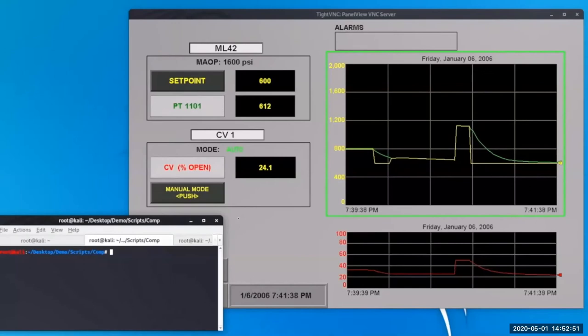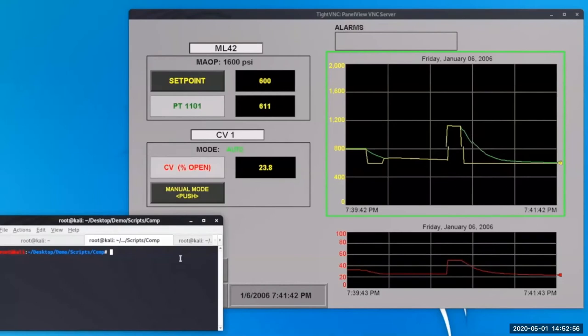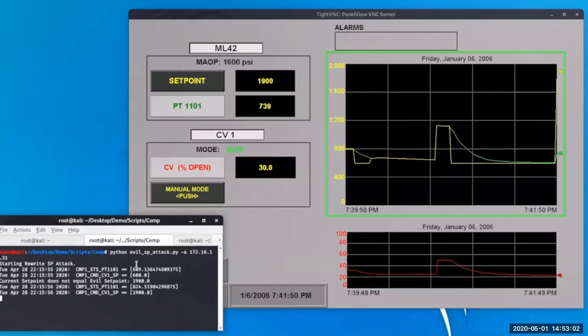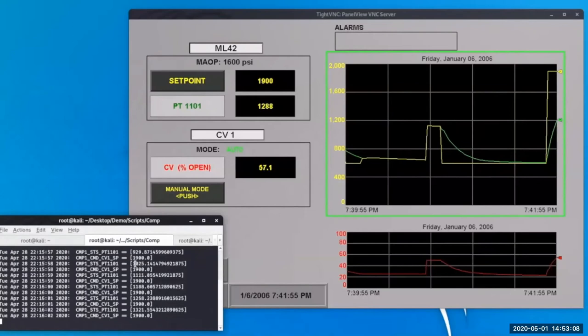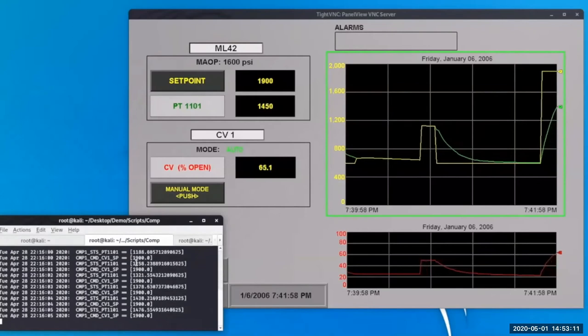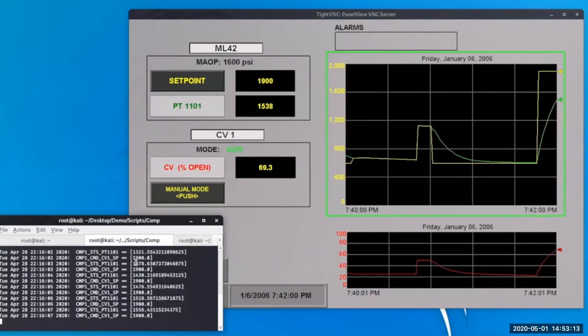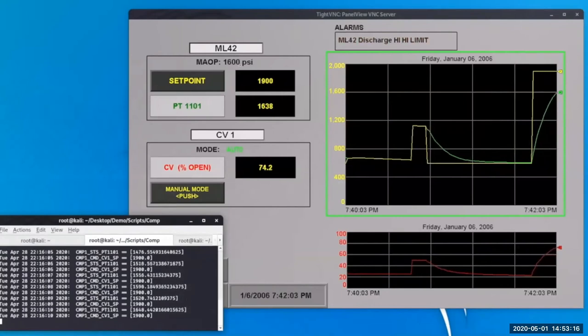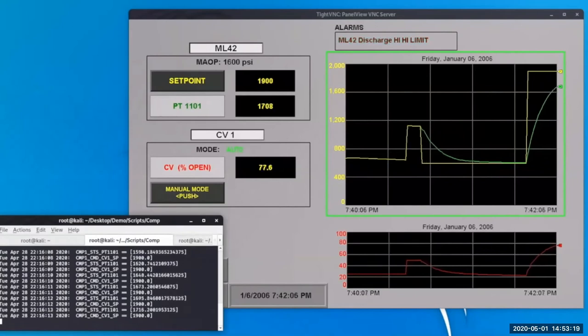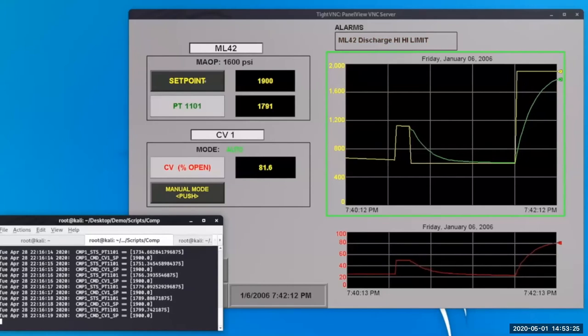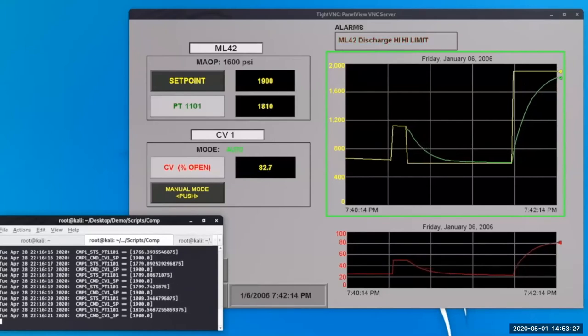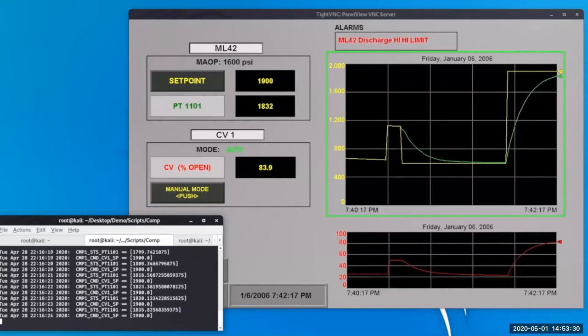What if we were able to bypass the HMI and directly write into the set point value? In this first attack, we're going to put a set point value to the tag and say we want it to go to 1900 PSI. The controller — the PLC — receives that value. It does not have any means of sanitizing inputs, so it doesn't have the same blockage the HMI has to prevent the tag from being set higher than 1600 PSI.